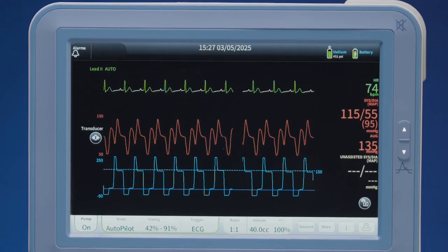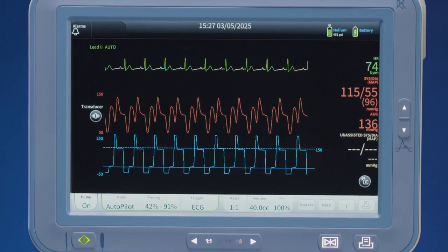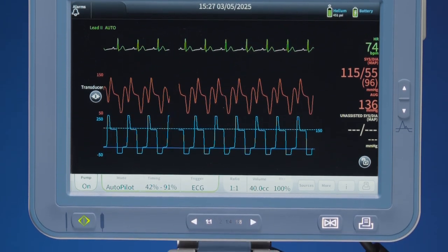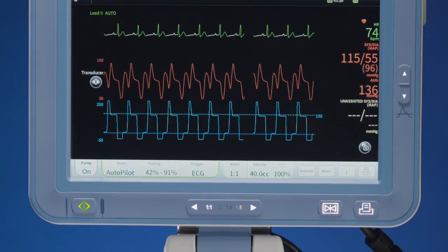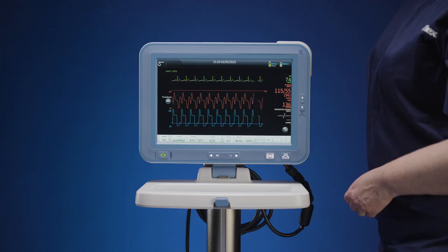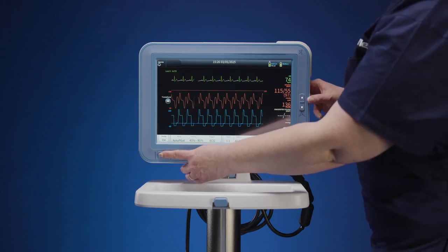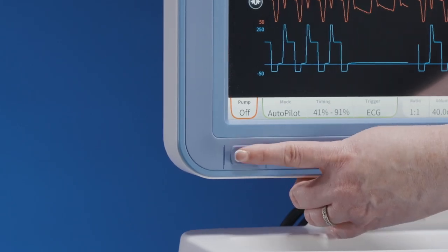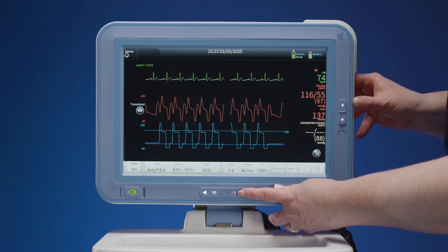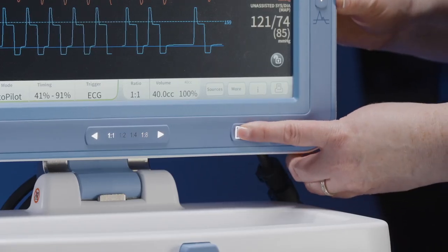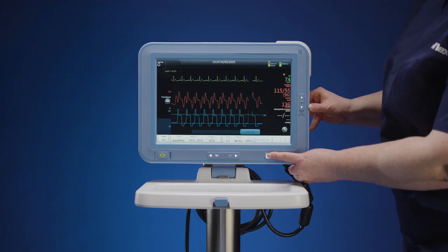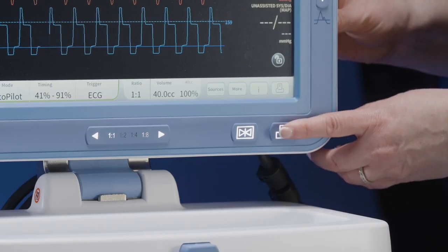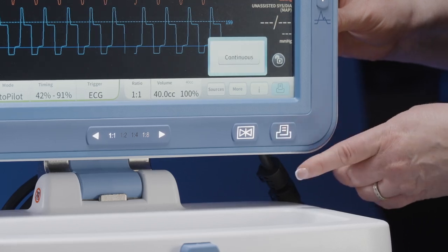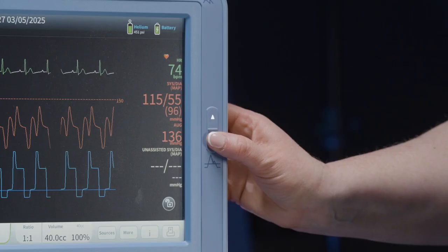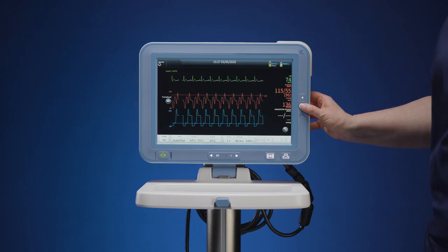The display module includes a touchscreen interface for most operations. There are selected hard keys for the frequently used keys and safety functions. The 6 hard keys include an on-off pumping key in the lower left corner, the assist ratio key in the center of the control display, a freeze screen key, a recorder on-off key in the lower right corner, and the cursor up and down key on the right-hand side of the control display. These hard keys are always active even when the touchscreen is locked.